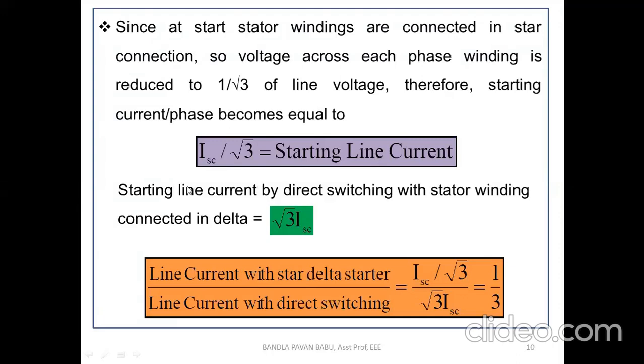Whereas the starting line current by direct switching, with the stator winding connected in delta, is root 3 into ISC. So if, without using any changeover switch, we directly connect the machine, which is delta connected, the value is root 3 times the short circuit current. Now take the ratio. Line current with the star delta starter is ISC by root 3. Line current with direct switching is root 3 into ISC. So the final value is 1 by 3 times.